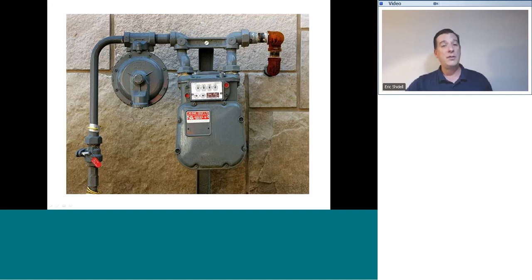You will use this valve to shut off the gas supply to the building if you're going to be doing any work on the piping or replacing appliances or doing anything like that. This is where you will kill the gas supply to the building. That is the only thing that you can really do out here. Now, up in the upper right hand, from this union fitting right here at the outlet of the gas meter to the right, that's customer-owned property, and you can do whatever you want on that end.